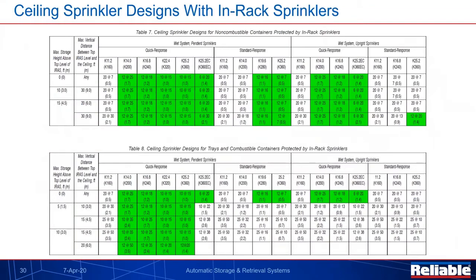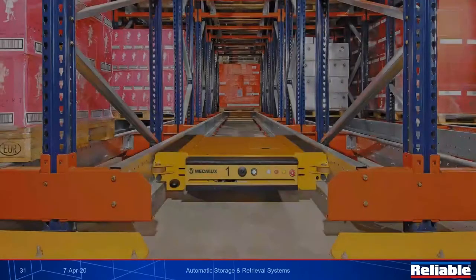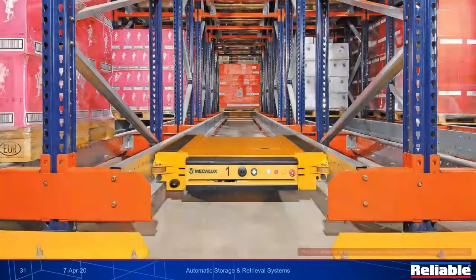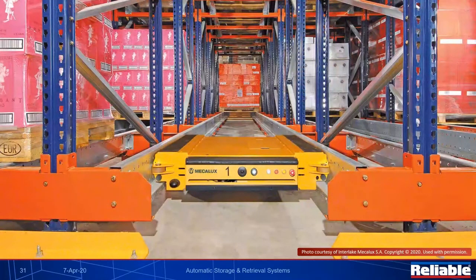With our ceiling sprinklers, we will need to calculate those in addition to the in-rack sprinklers. We have tables 7 and 8. They're going to provide guidance on how to do that. Next, we're going to talk about section 2.2 of FM 8-34. This one deals specifically with rack structure ASRS.